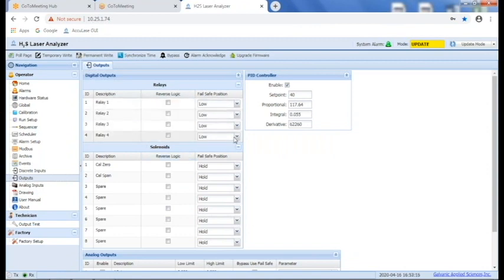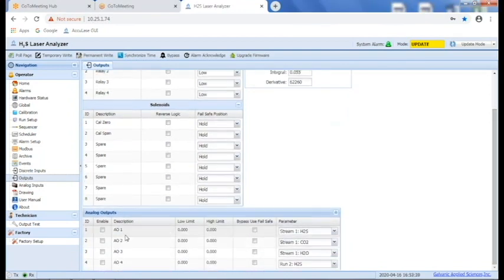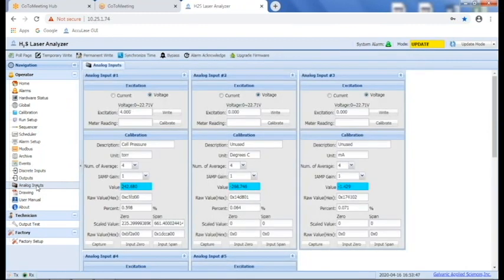For outputs, we have the relay outputs. You can set them to be fail-safe or not. The solenoids as well in a similar way. And down at the bottom here, we can assign the analog outputs with high and low limits. You could also indicate whether or not you want to use the fail-safe value when you put the analyzer into bypass. We also have some analog inputs. These are typically associated with the analyzer, for example, the cell pressure and temperature, things like that.